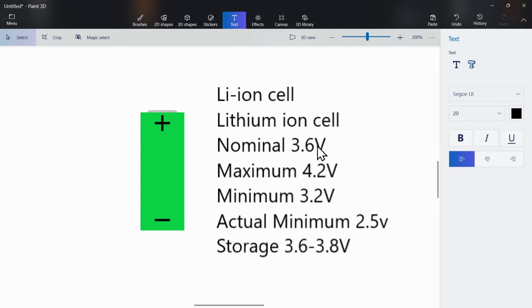This is kind of like the mid-range voltage that we base all our values on. The maximum voltage is 4.2 volts and the minimum voltage is 3.2 volts. However, the actual minimum is more like 2.5, but there's not a huge gain in draining your batteries that far, and it just makes them degrade faster, and there's a risk it'll go way under 2.5 if you just forget about it for a bit. So most of the time we treat it like the minimum is 3.2 volts.